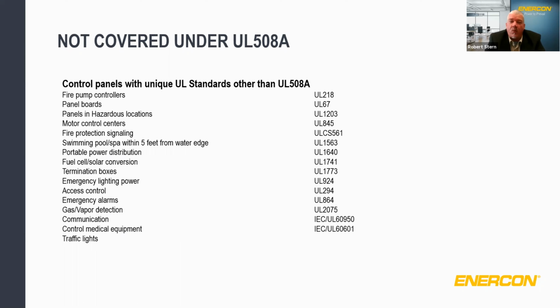So there are obviously a wide range of different industrial control panels, or things that look like an industrial control panel under the UL 508A standard, that are actually not covered under 508A because they have a specific UL standard. You'll see fire pump controllers, panel boards, panels for use in hazardous locations, of course, motor control centers, which are covered under UL 845, fire protection signaling. Again, talking about swimming pools and spas, if it's within that 5 foot from the water's edge, that's covered under UL 1563. Portable power distribution, fuel cell and solar conversion boxes, termination boxes, emergency lighting applications, access control, emergency alarms, anything with signaling basically is not covered under 508A.